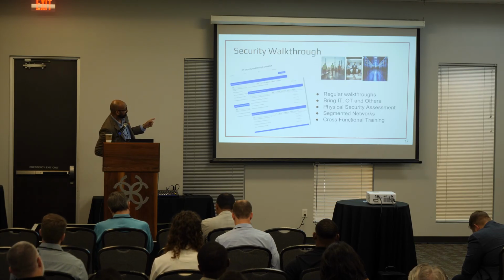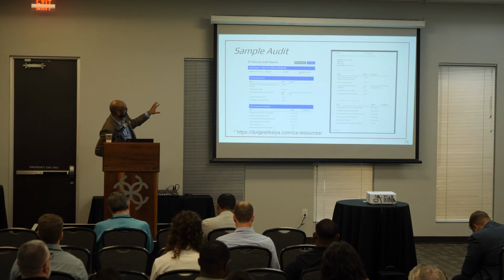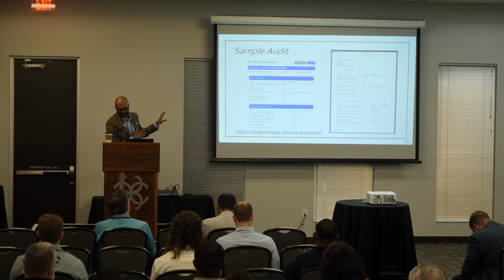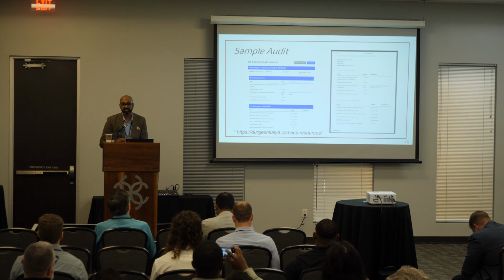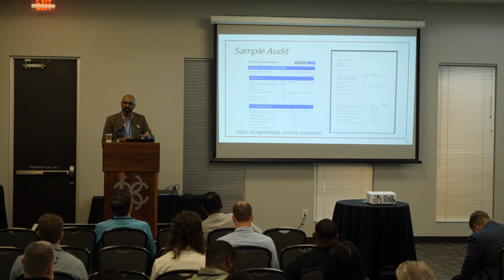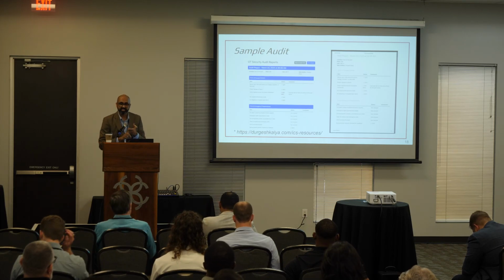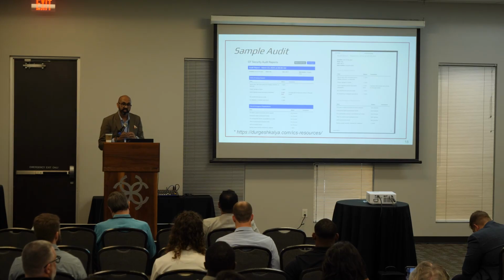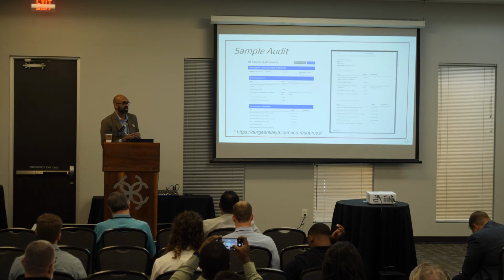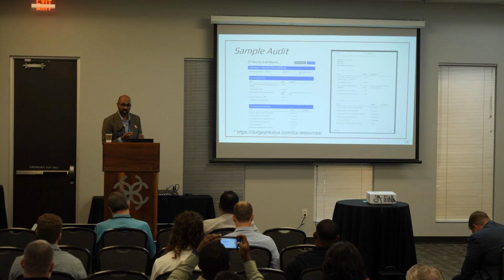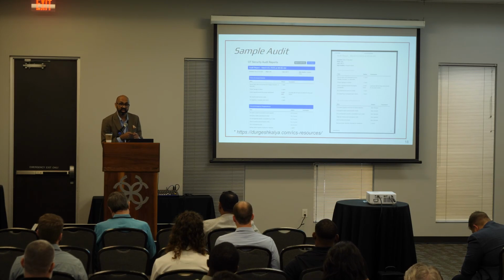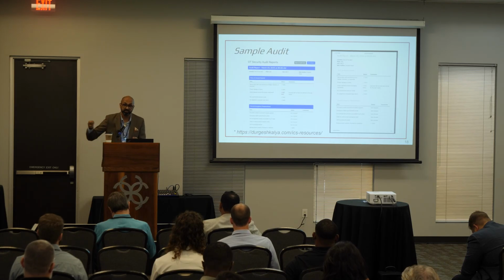All right, so the security walkthroughs, these are some of the reporting. This is not really on the computer. We usually actually print it out. We are trying to go into a software-based approach where you can take a tablet with you and do checks. But typically, you're looking at access control, you're looking at OT network, you're looking at rack management, you're looking at how cabinets are locked. Sometimes cabinets have a lock and the key is sitting right in it. No, you need to be able to manage that. So that becomes key management, where you put the keys in a box and somebody has access to it. And so that comes up through these security audits.